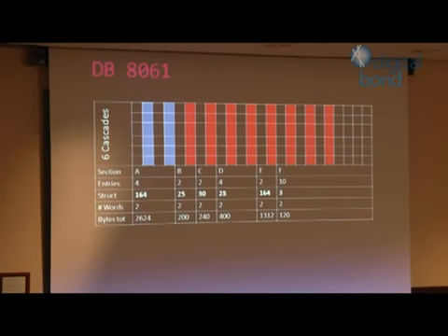And there is some supporting evidence for this because we have a pretty good idea of what DB8061 contains. This is what you see here. Actually, it's just one freaking big addressing table. It holds I/O addresses. And you would, with a high degree of confidence, find something like this in the legitimate application.